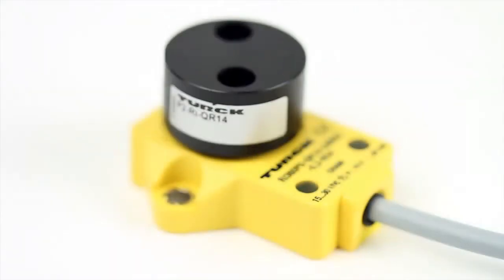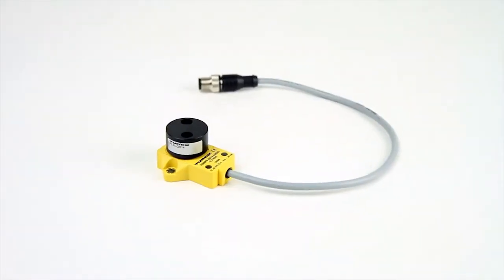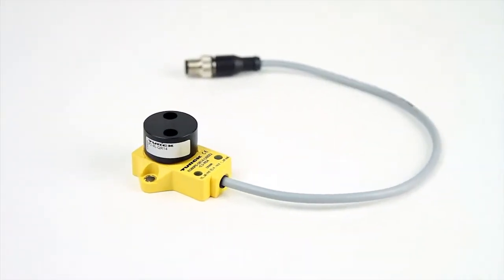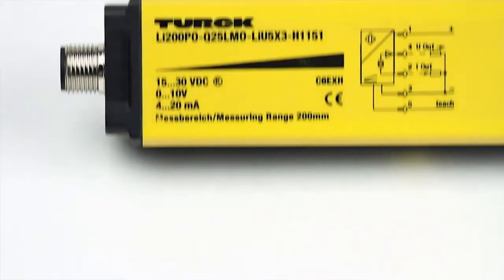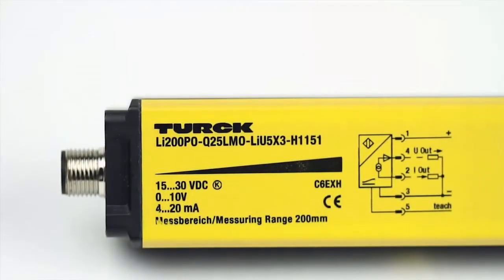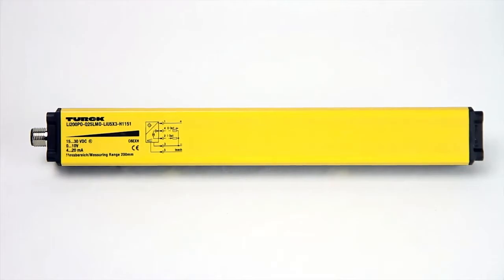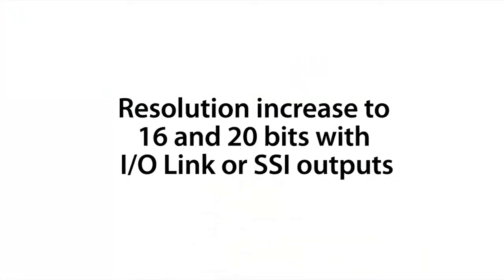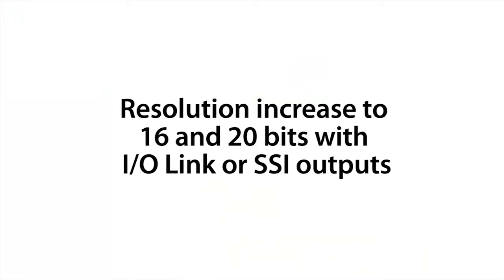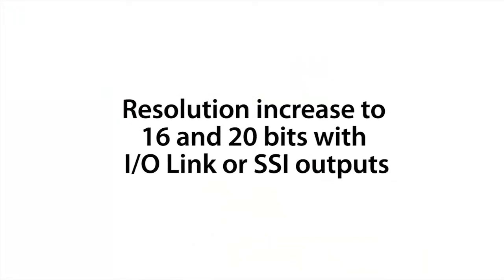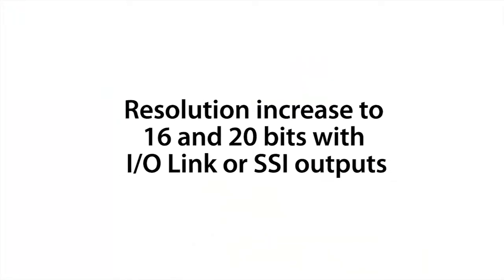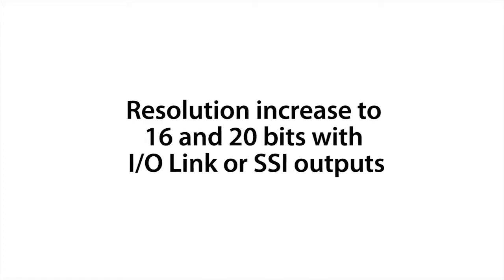Inductive position sensors have 12-bit resolution over voltage and current ranges. However, by utilizing the enhanced versions with IO link or SSI outputs, those resolutions increase to 16 and 20 bits respectively.